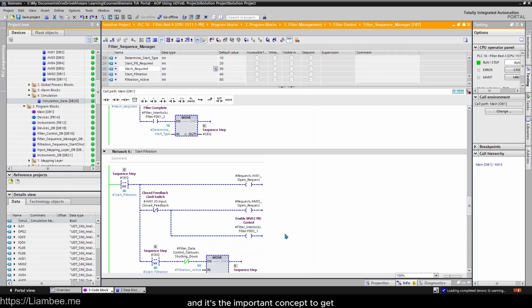And it's an important concept to get in your mind when you're developing asset-orientated stuff, because what we always want to try and achieve is that the asset is containerized and all of its functionality is containerized. All of the control is containerized. And then you have links that link stuff together, things that enable other things, things that inhibit other things. But when you're making your modifications, you're not changing core control aspects.